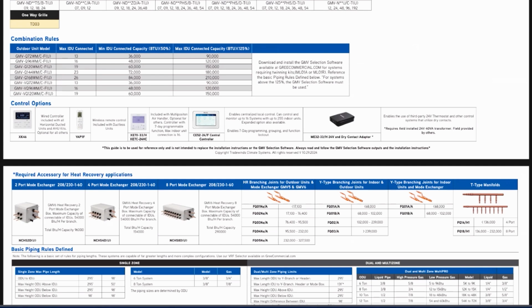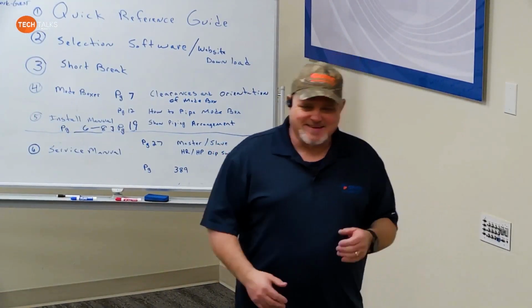And I've had guys ask me, well, can't I just change the wiring and make the transformer hot all the time? A guy could, but I can't condone it. The reason is I can't tell you to do things to that machine that take away the UL listing. If you choose to do something like that, keep in mind you're doing that on your own. I'm not telling you no, I'm not telling you yes. I'm going to give you the shoulder shrug because I can't condone it.